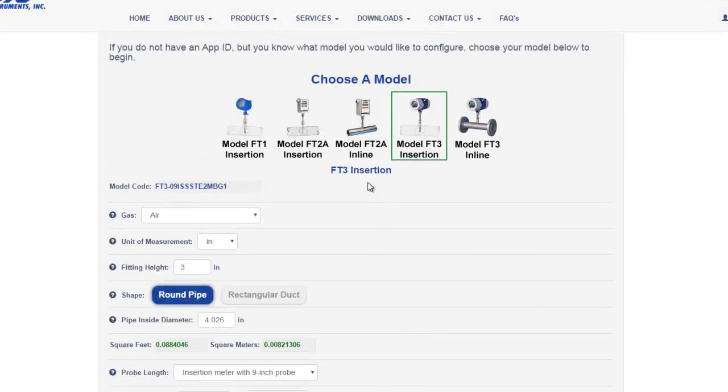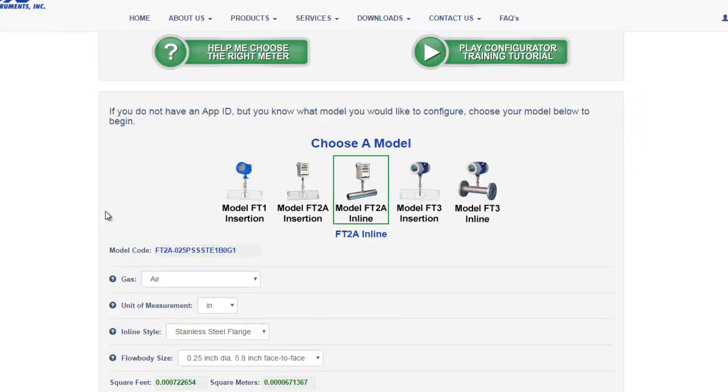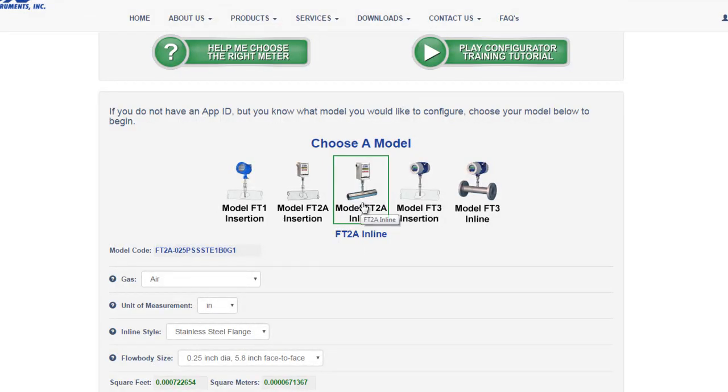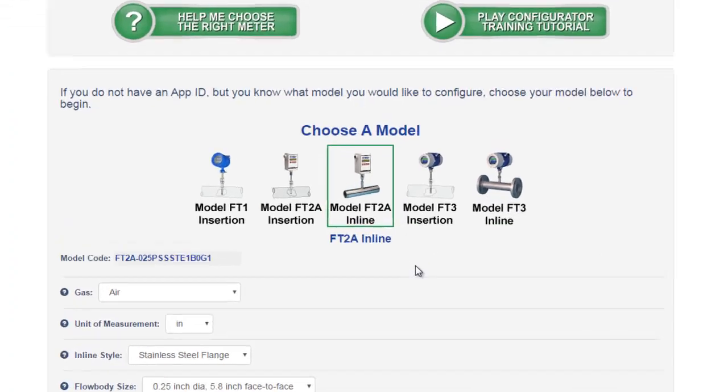Let's look at a model FT2A inline. Fox inline meters are only available in certain pipe sizes. The meter is built and calibrated with the spool piece section that we call a flow body. The flow body can either be configured with threaded connections on each end, as shown here with the FT2A inline, or flange connections, as shown here with the FT3 inline. Let's go through a quick configuration.